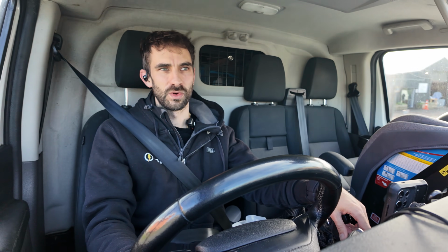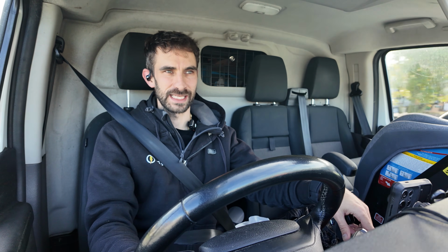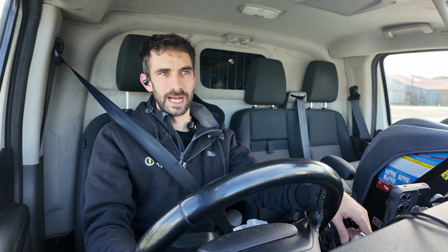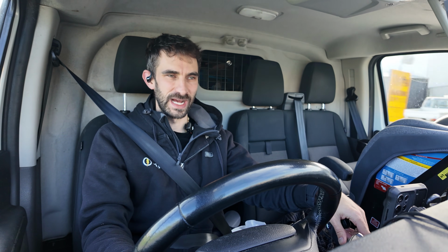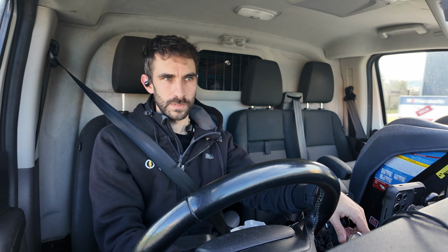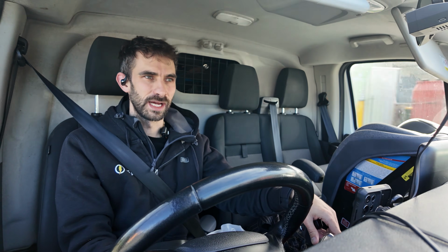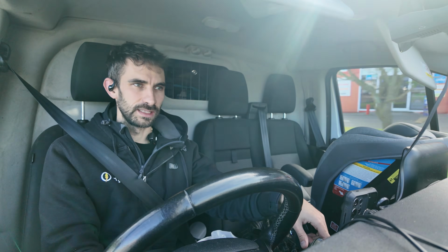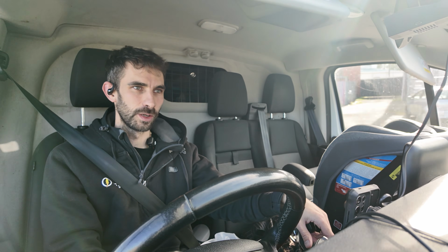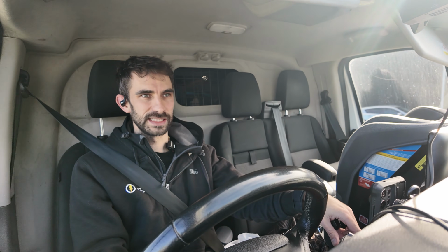So sure, your electricals in your house are going to get pretty fried, but the earth rod will help do something to take that voltage away and to cause the high voltage fuses to trip a bit faster. And maybe it helps against lightning strikes too. But that's not something the electrical legislation talks about. If that's the job it's doing, it should at least be described that here's the real benefit you get from these.